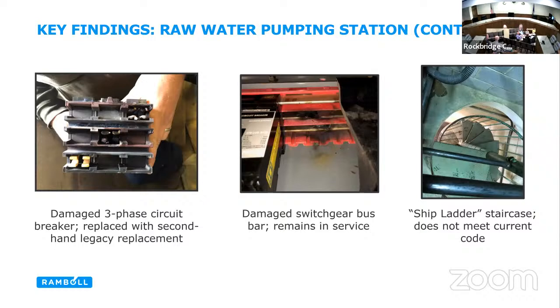That becomes an issue on the raw water pump station, our only raw water source, because of the electrical codes—if we have another failure with these breakers, this main bus bar, and this electrical panel, we're going to have to build a new panel to meet current codes. We don't have enough room in the building to meet current codes for a new panel, which means we'd have to expand the building in an emergency, running off a diesel pump until we could expand it enough to put in a new panel, new breakers, and hook up to the rest of the 1975 vintage equipment.